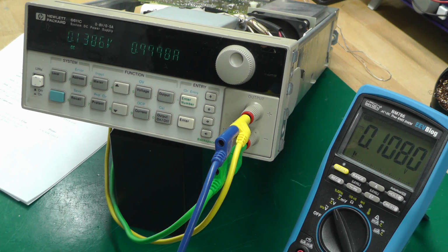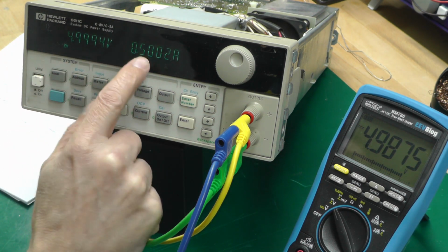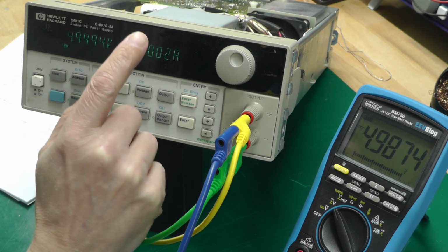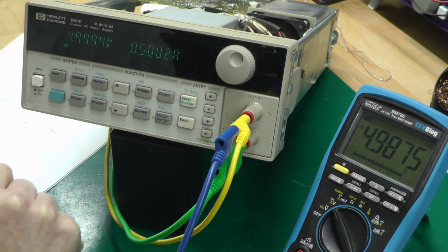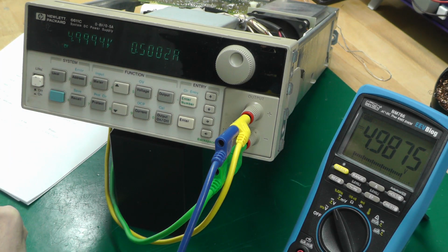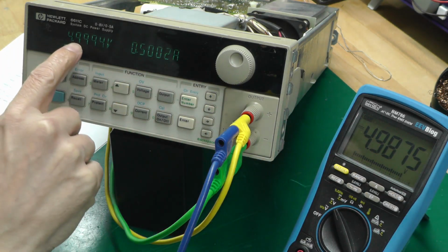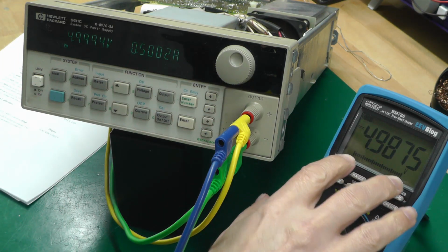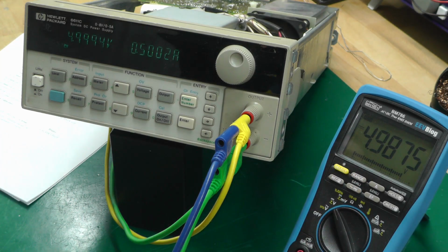So let's adjust that electronic load down to something less. So let's put it to half an amp. Turn output on. So now I've got it set. Yep, half an amp, 0.5002. So the current is spot on. It's actually more accurate than the voltages at the moment. So you can see I'm getting a little bit of a difference now. That's probably a volt drop on these banana setups that I've got here, and obviously the internal wiring within the power supply as well.